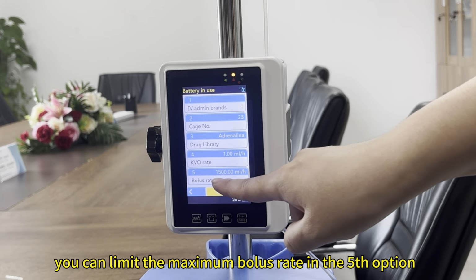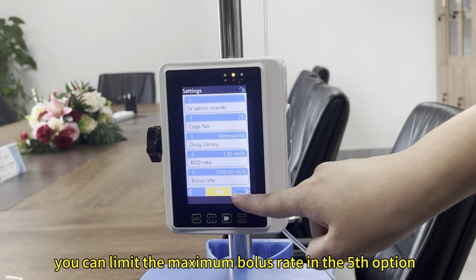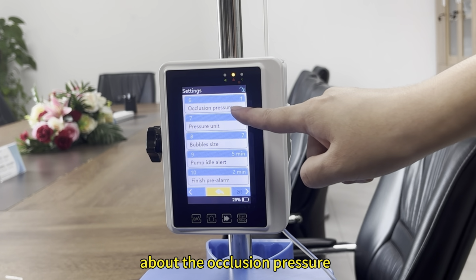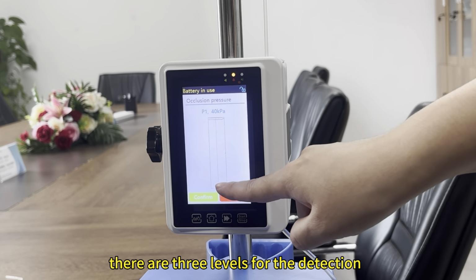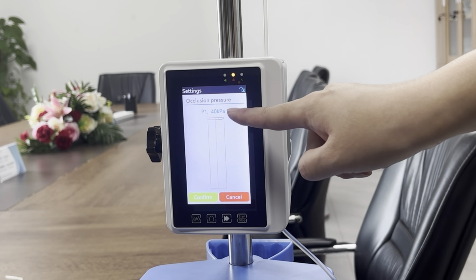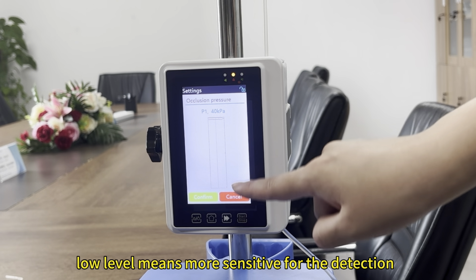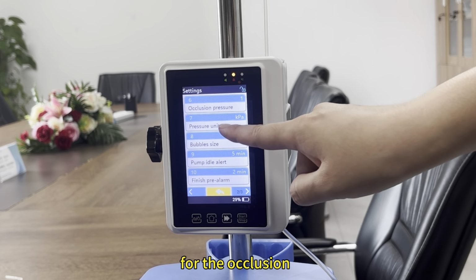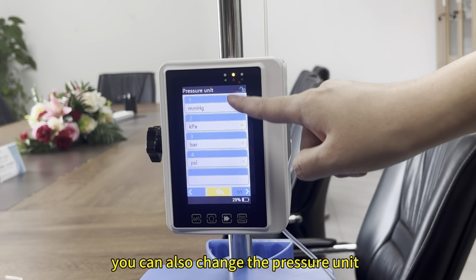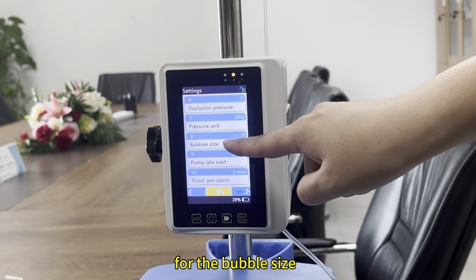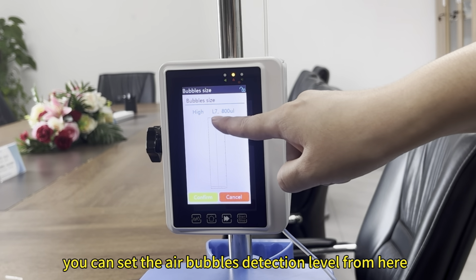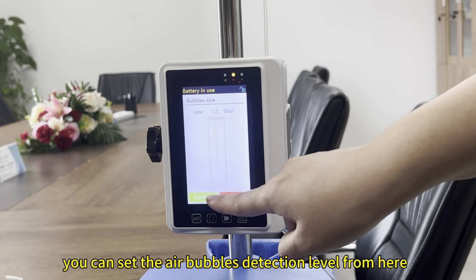You can limit the maximal bolus rate in the 5th option. About the occlusion pressure, there are 3 levels for the detection of the occlusion. Low level means more sensitive detection of the occlusion. You can also change the pressure unit. For the bubble size, you can set the air bubble detection level from here.